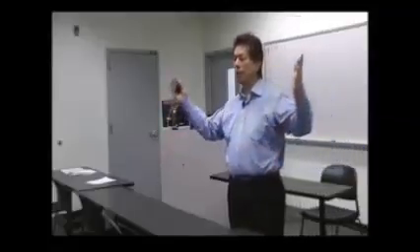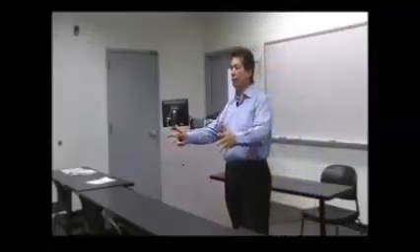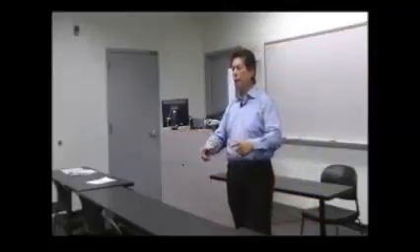So the building was never designed to have vent work to that room? No, because there was a vault. Once you walked into the vault, all you had was lights. They turned the vault into a meeting room. So part of the design was perfect. The design had coring. The design had a fan coil unit above that vault. Everything was set, easily accessible for maintenance up on top of the vault, never had to access the room.